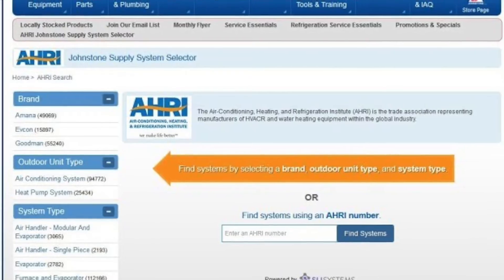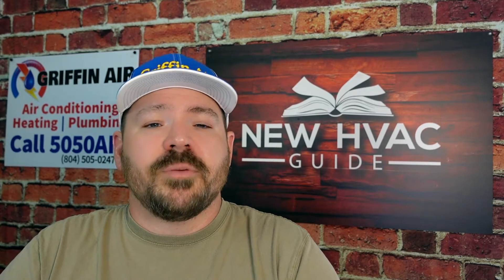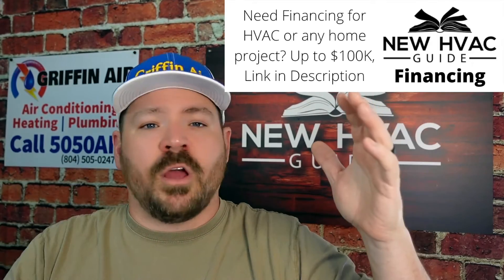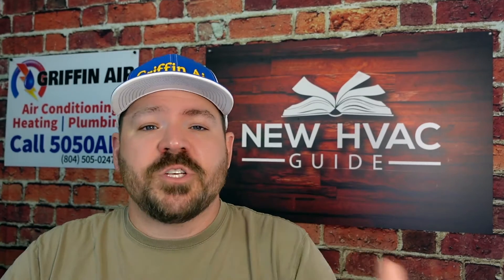I was just helping somebody with the guide the other night. They figured out after hearing me say that in another video that a contractor was installing a system that was not an AHRI match. To meet certain standards, if a manufacturer says they're selling you an 18 SEER system versus a competing 14 SEER system, they're claiming it's more efficient and you should get more energy savings. But if you're using it matched with an old or mismatched system, a different brand or different type, that throws those ratings off. You won't see as much savings. Most good contractors can provide you with an AHRI certificate to prove it's a proper matchup.